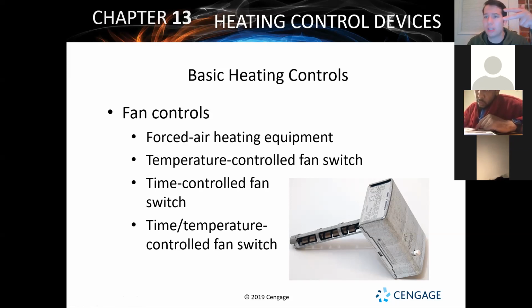The third setting is a limit switch, and that's usually set at about 200 degrees so that if the heat exchanger is overheating and gets up to 200 degrees, it shuts the furnace down and it kicks the fan on automatically, forces the fan on until it gets back down to that cooled off temperature, and then the fan will shut off. So these are pretty interesting devices. They're old school, but they work really, really well, and they're pretty simple and basic.